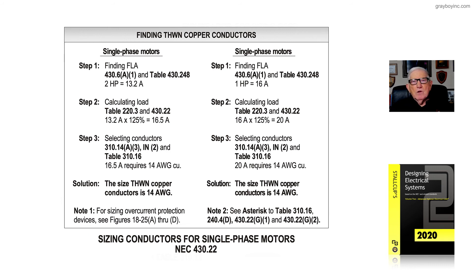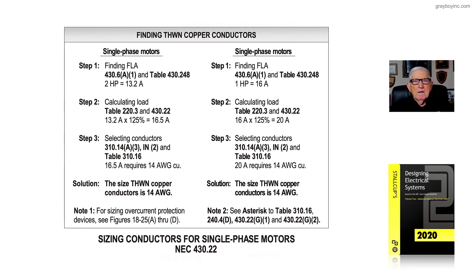The full-load current comes from Table 430.248, as instructed by 430.6A1. As a rule of thumb, sometimes an electrician will take the 16 amps and round it up to an even unit number — round it up to 20, then apply 125% to size the conductor. It might be a little larger, but it will supply the amps needed to drive the motor and the load.